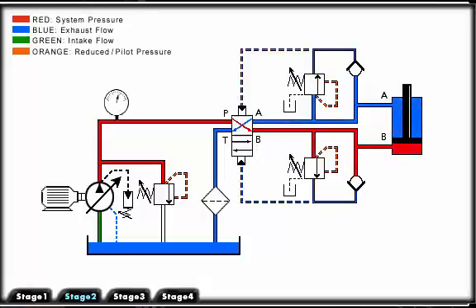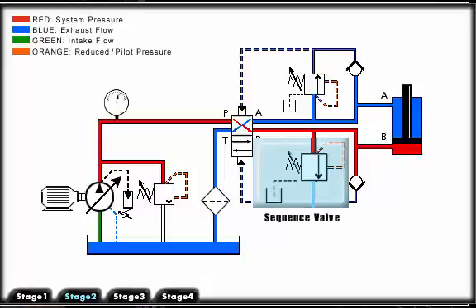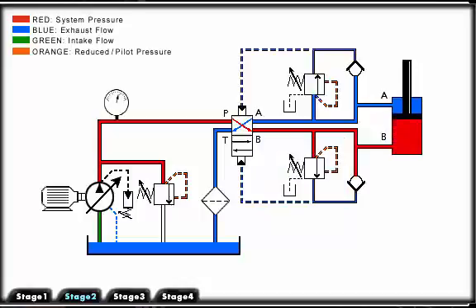Pump flow is now directed to the lower circuit, and the flow here goes to three places. It is blocked at the check valve and blocked at the closed sequence valve. But flow to the B port of the actuator is open. Flow in the port will apply pressure to the piston and extend the cylinder. Flow out of the A port is blocked by the upper check valve, so it flows through the directional control valve to the tank.